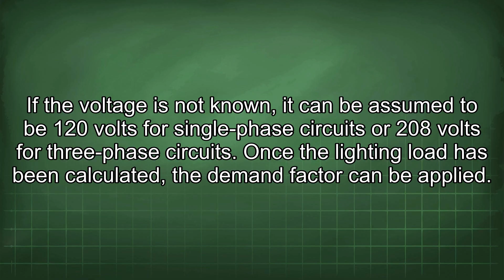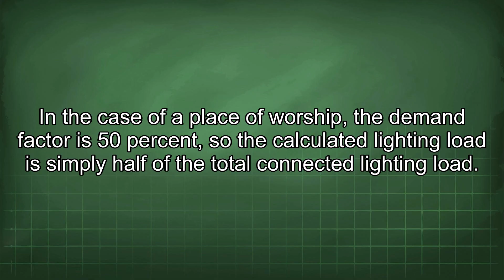Once the lighting load has been calculated, the demand factor can be applied. In the case of a place of worship, the demand factor is 50%, so the calculated lighting load is simply half of the total connected lighting load. For example, if a church has a total connected lighting load of 20 kVA, the calculated lighting load for service sizing purposes would be 10 kVA after applying the 50% demand factor.